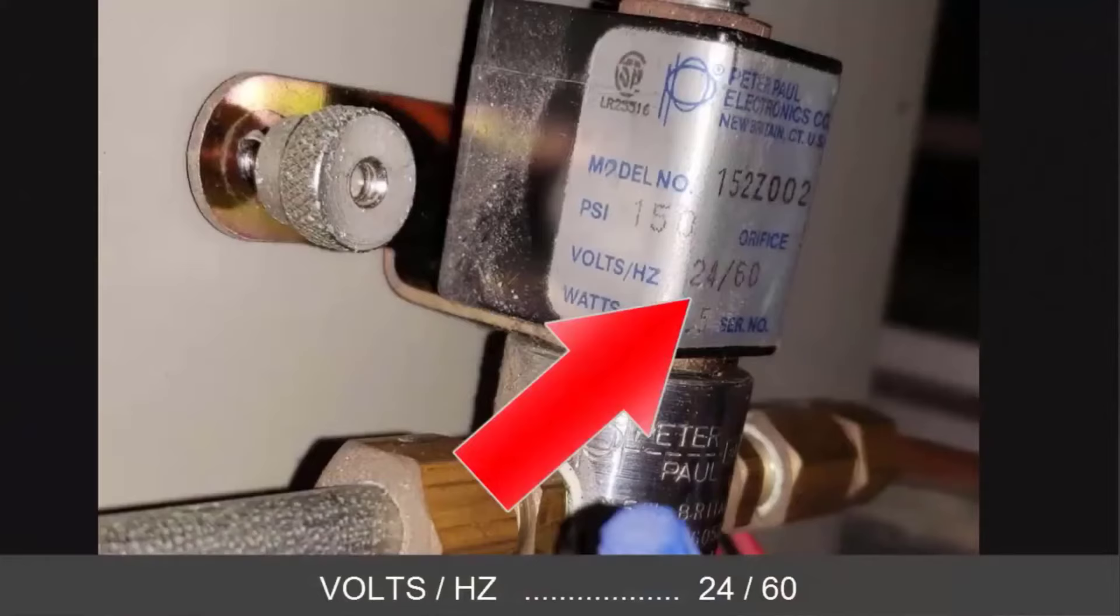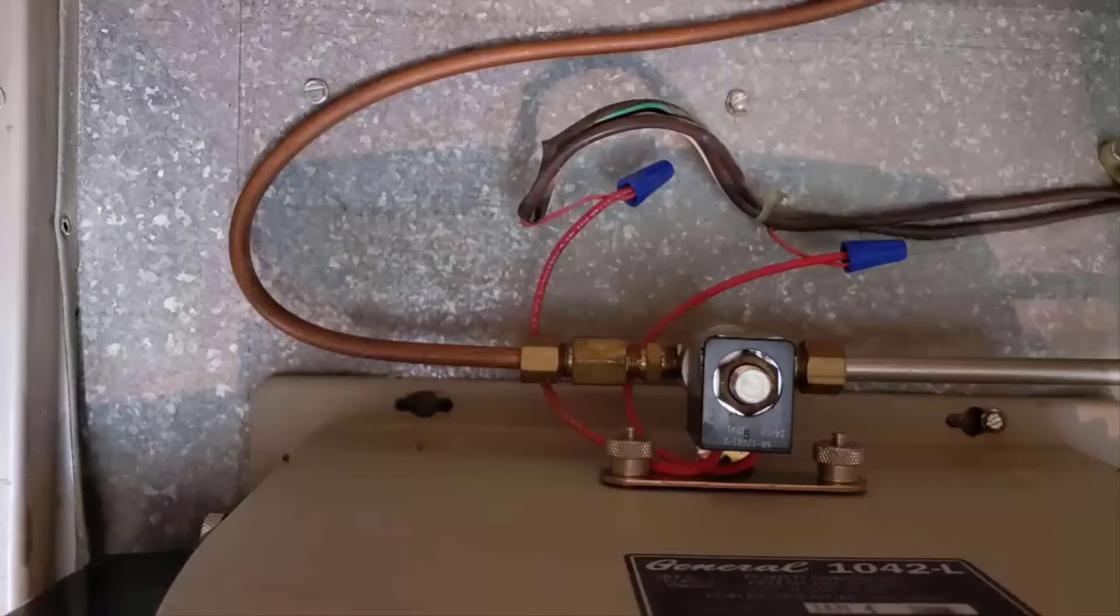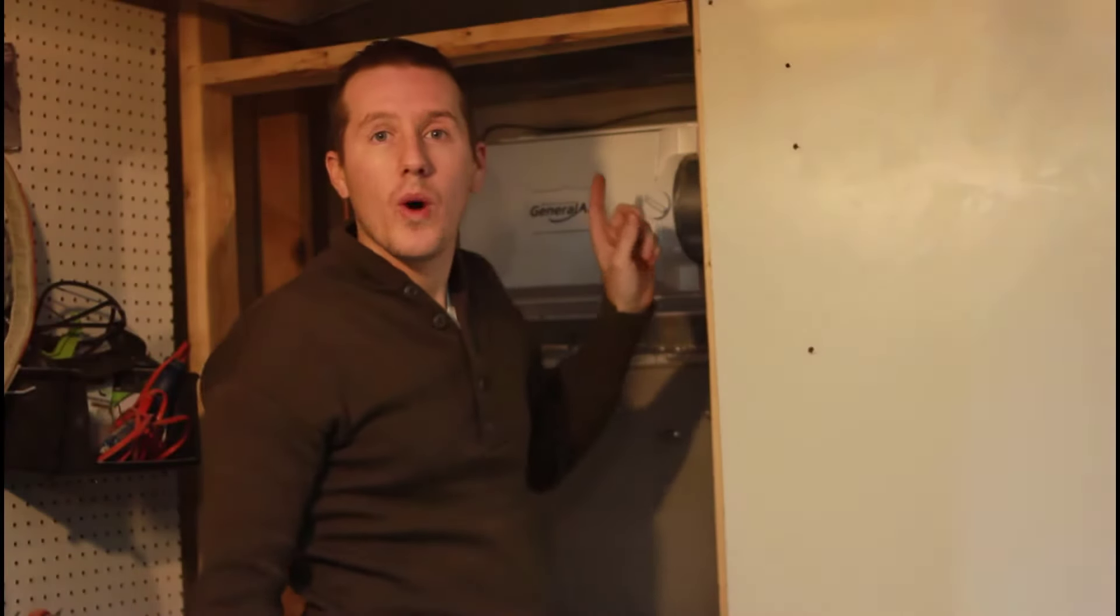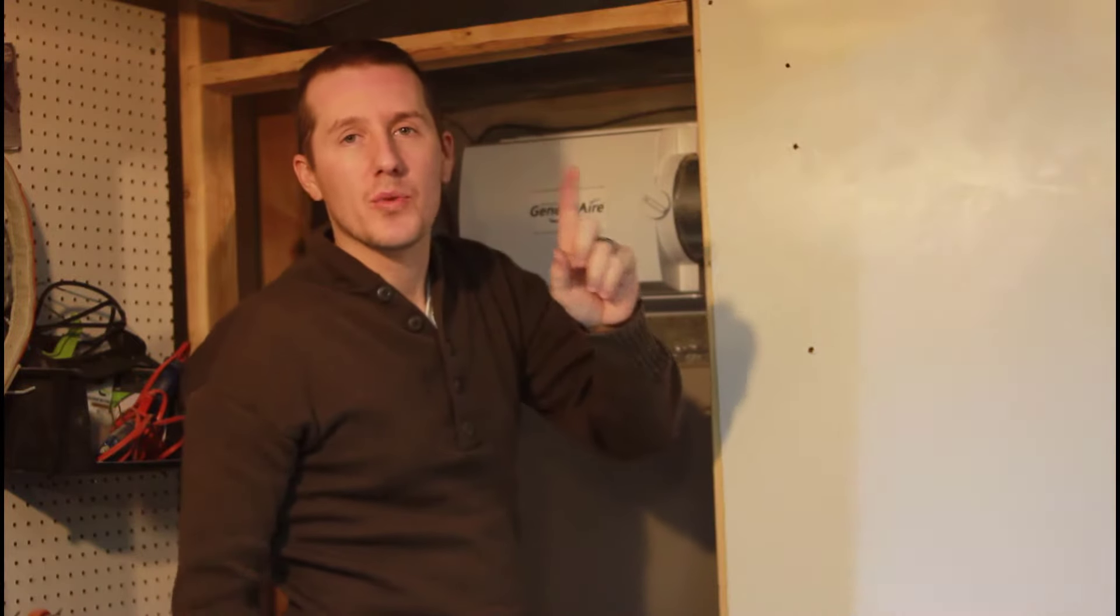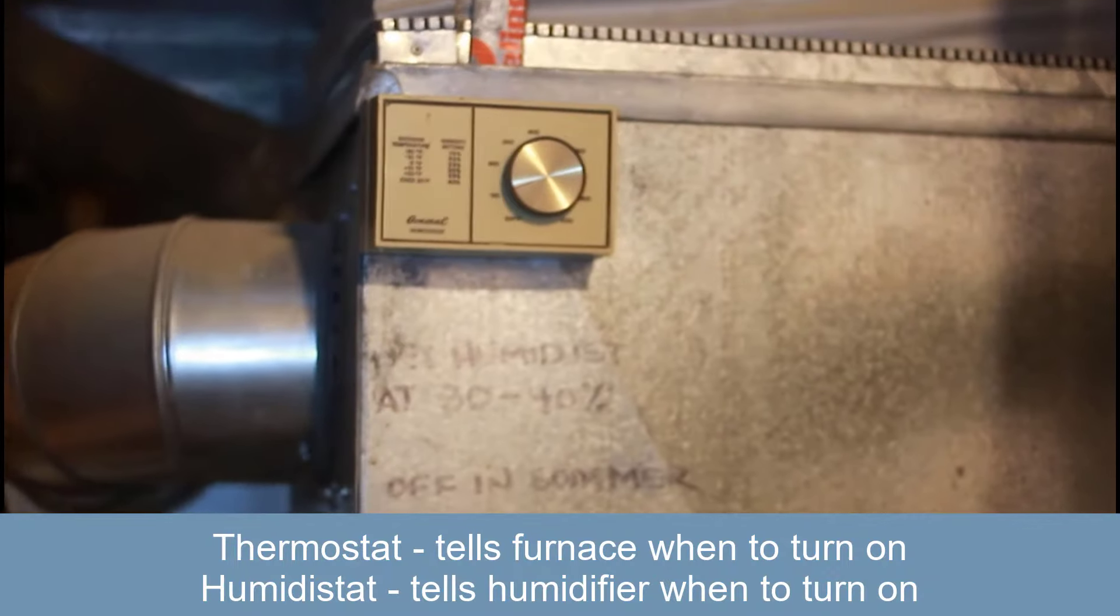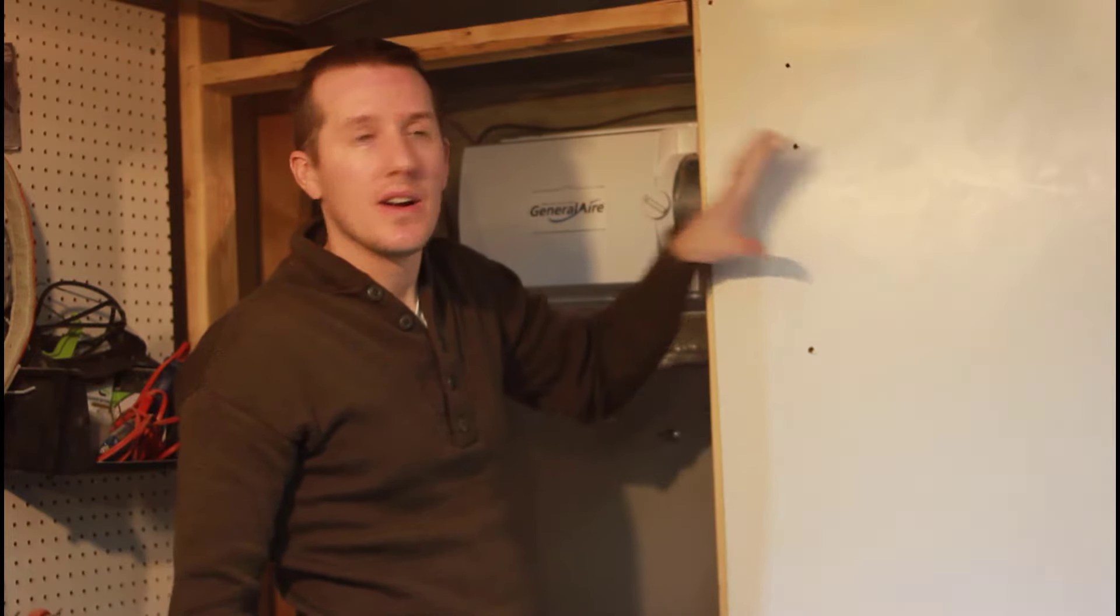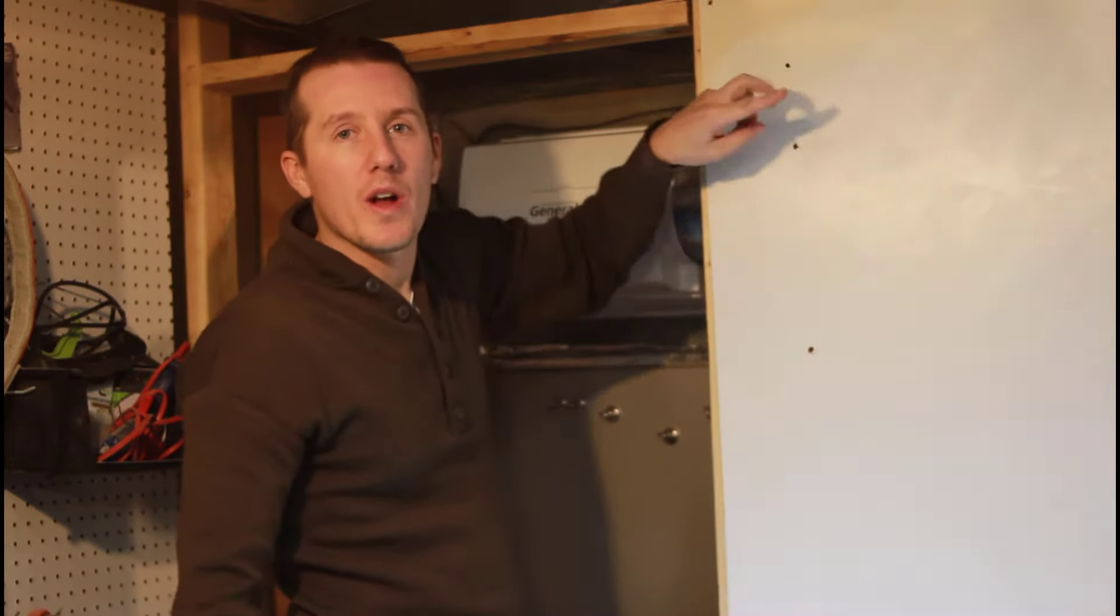Now I said you are going to have to run a wire from the transformer, the circuit board, to the solenoid. You also have to run another wire, and that is the humidistat. You can put that on a wall, on the side of the furnace, typically is where it goes, somewhere easy access. Again, my furnace already had that on here from the old humidifier, so I am going to leave it on there. But again, you would have to run another wire to the solenoid. So there are actually two wires coming to this unit.